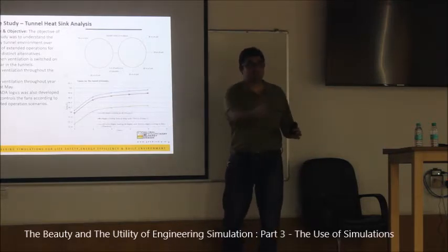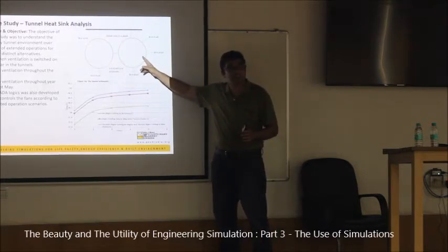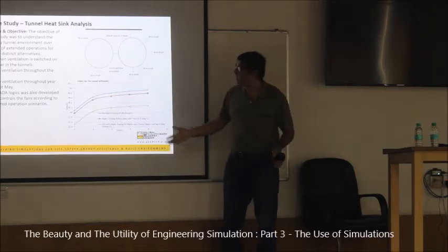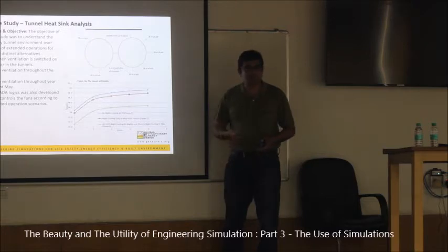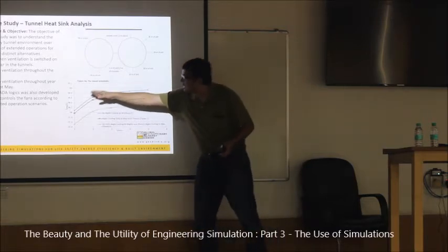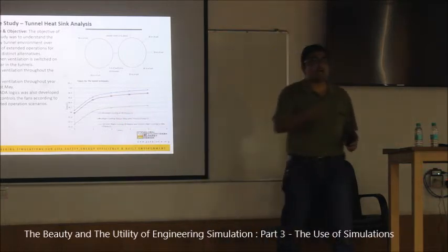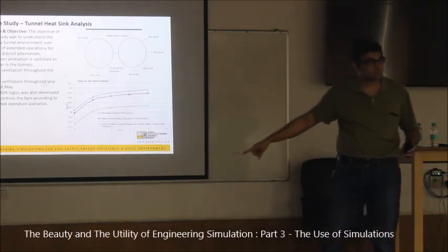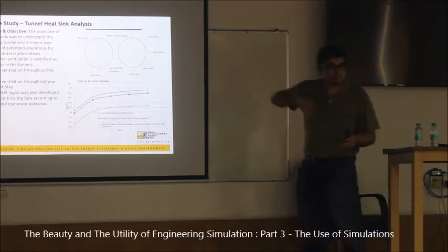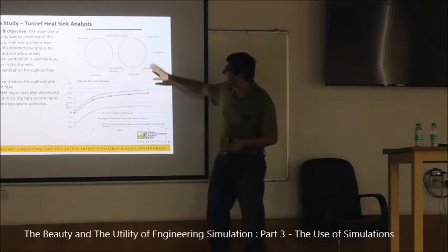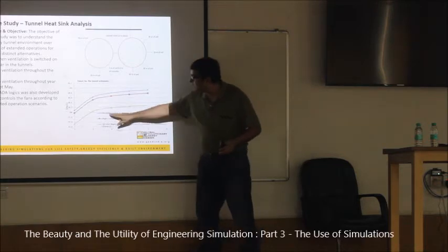As soon as you have larger airflow, the Nusselt number makes sure that the heat transfer through the surface of the tunnel is more. So you regulate that. You know the frequency of the train, you know how much heat it is pouring in, and you know that up to 30 meters of radius of the earth would be impacted based on annual temperature changes. This is what you do after doing a sensitivity analysis. So you do simulation and then you apply various strategies, like night venting.